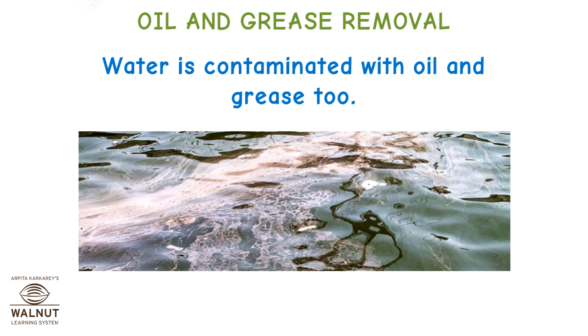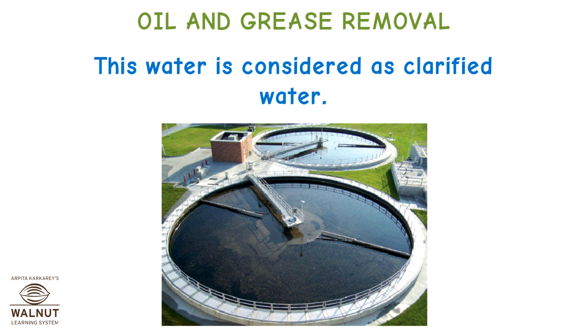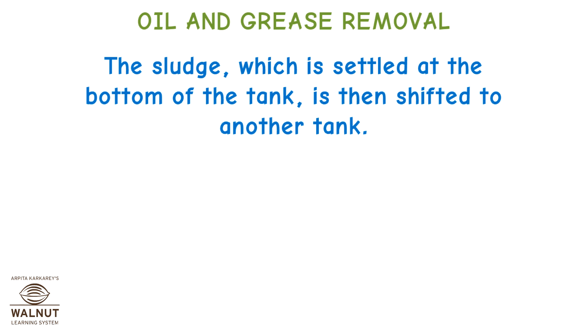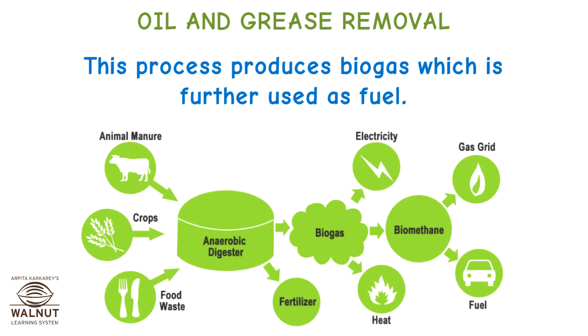Oil and Grease Removal: Water is also contaminated with oil and grease. A skimmer removes the oil and grease from the water, and this water is then considered clarified water. The sludge settled at the bottom of the tank is shifted to another tank, where it is decomposed by anaerobic bacteria — a process that produces biogas, which is further used as fuel.